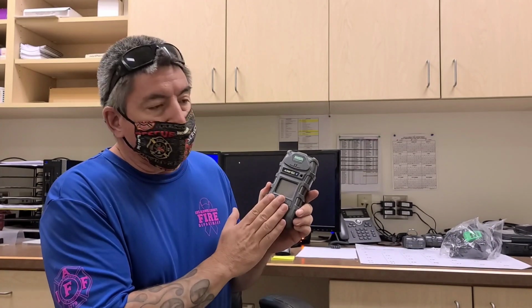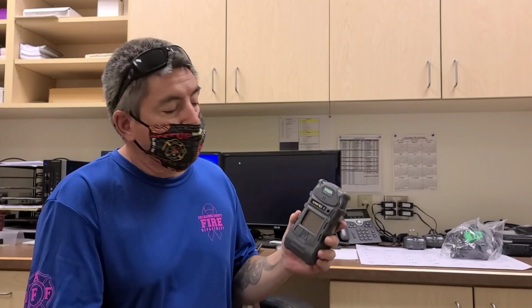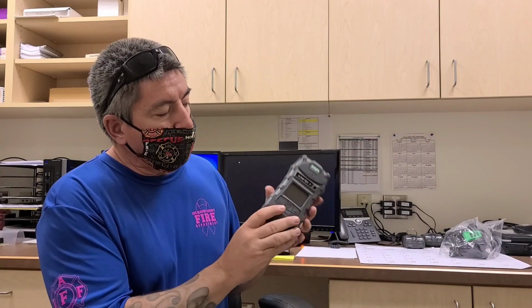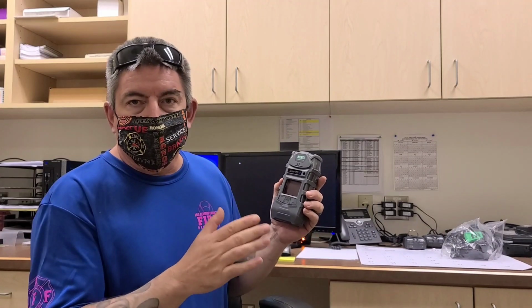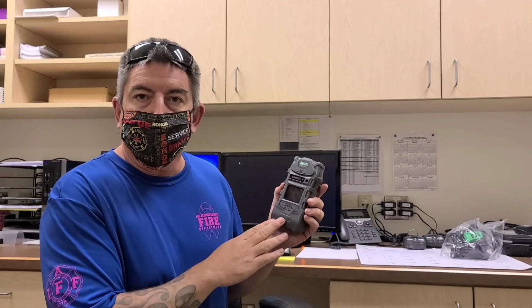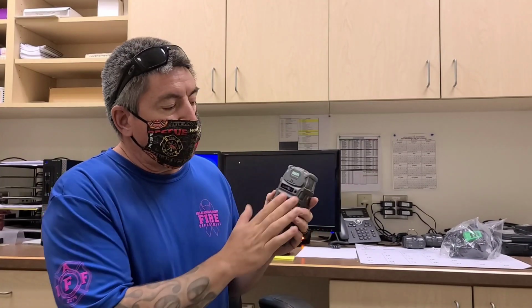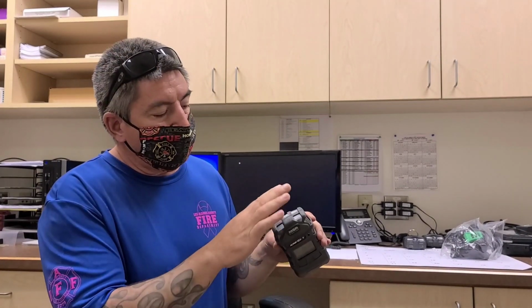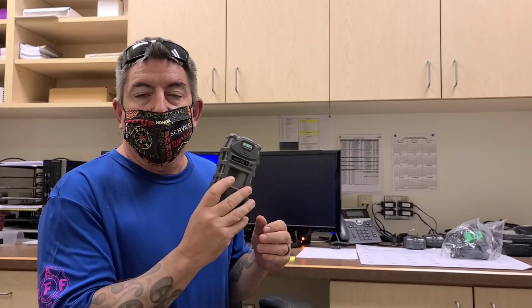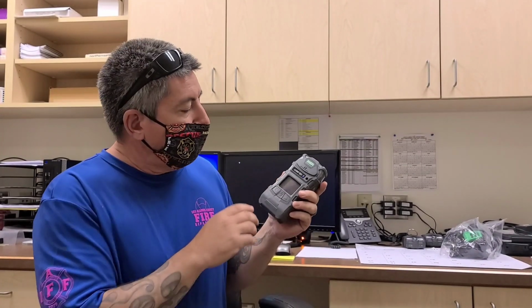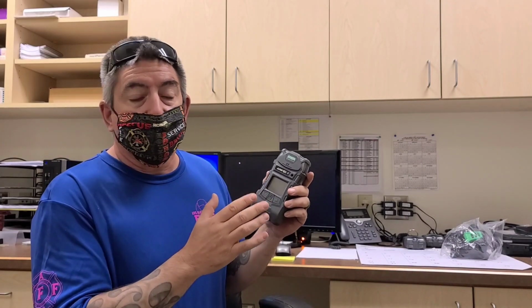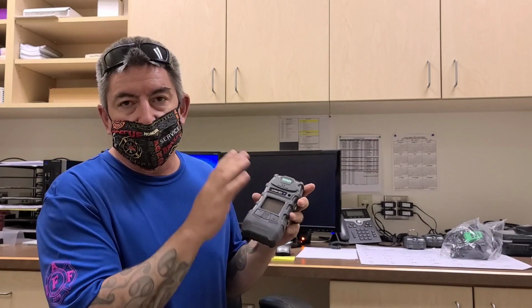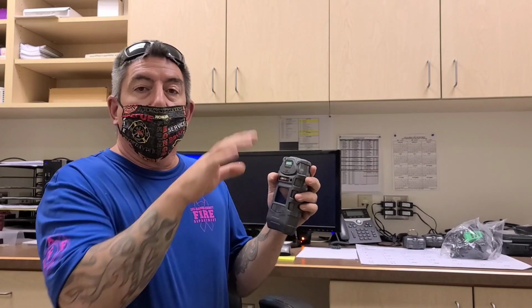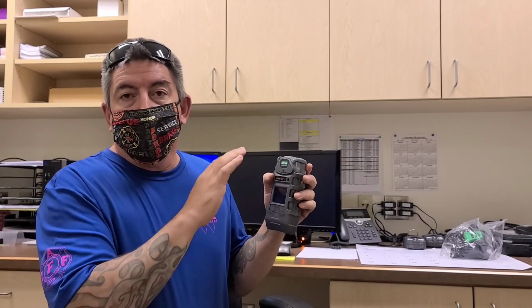But don't try to put this over the stove in the kitchen to see if it's working, or the exhaust of any vehicles. As well as keep it out of the way of any sprays, silicone type sprays like Armor All, lubricants that we use on nozzles. You don't want that to touch the unit at all or be anywhere near the inlet to the sensors. That damages these sensors inside here. As well as Cavicide, any kind of cleaning agents, we want to keep all that away from this unit. Try not to directly spray it or keep it in the vicinity of anything around that.